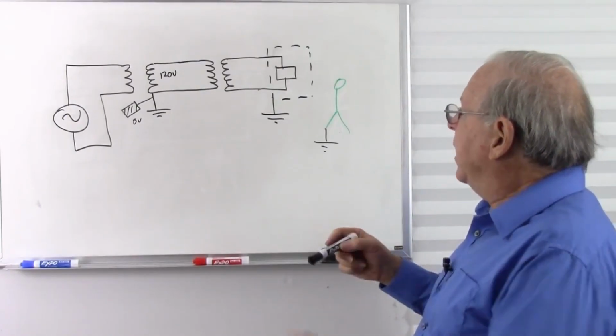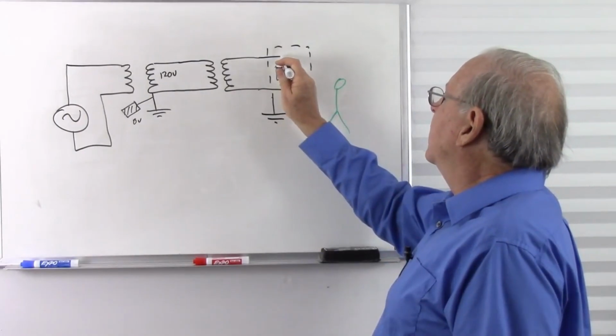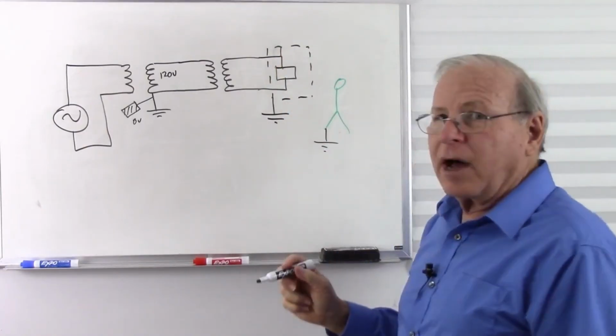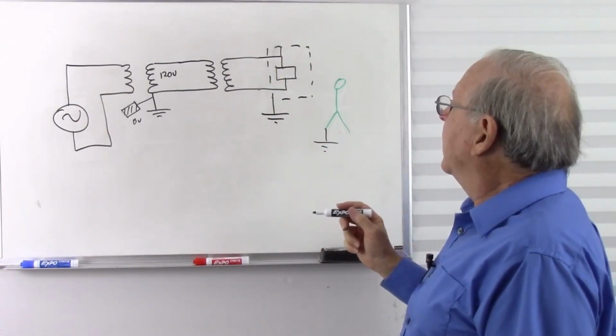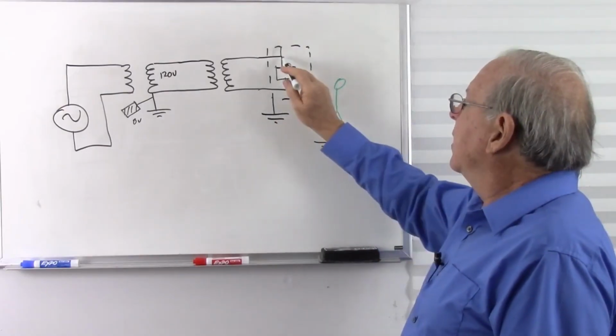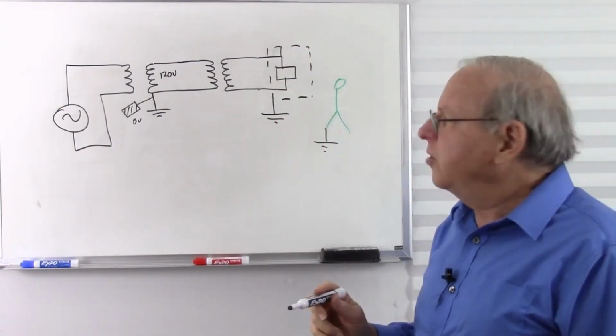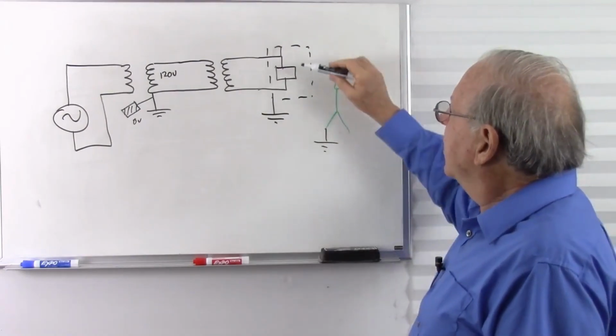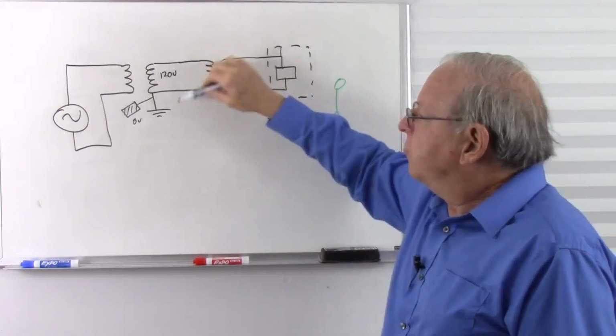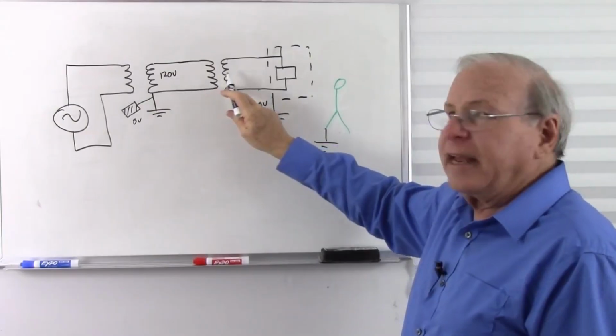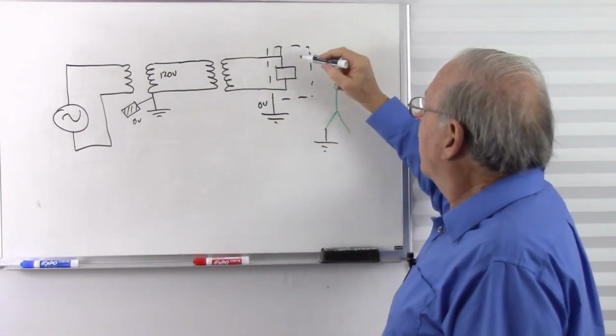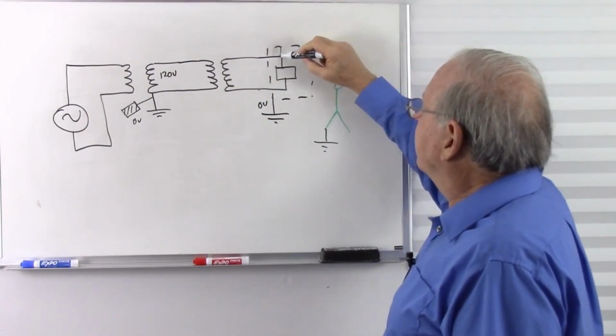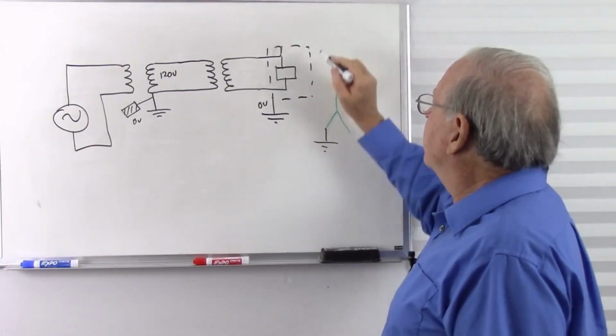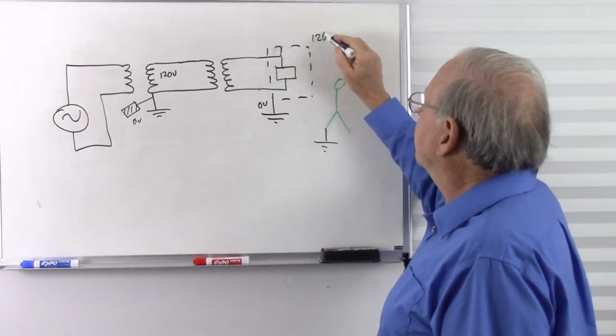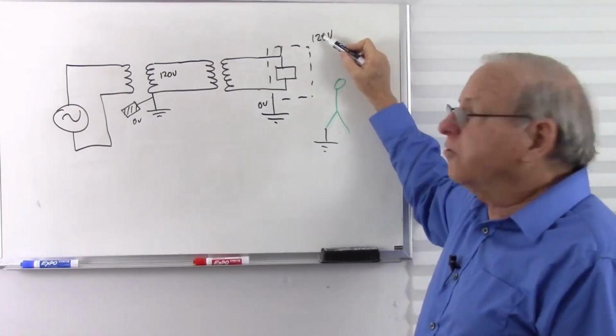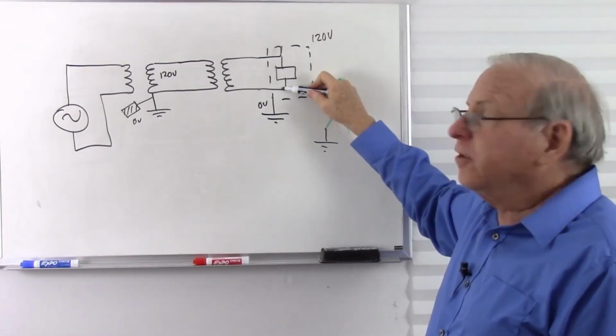What happens if there is a fault? Let's say this somehow gets connected to that box again. Okay, so that box is grounded, I'm grounded, I have 120 volts to that. What's it going to do? Well, nothing, because this ground is in reference to this part of the circuit. There's no galvanic connection over to here. So I get this connection to the frame. It's energized to, let's call it 120 volts, but that 120 volts is referenced to the other side of the transformer.